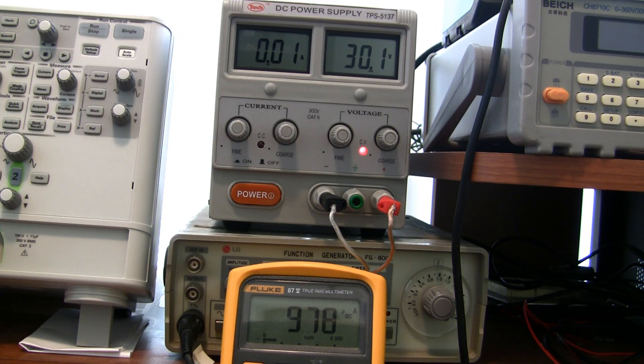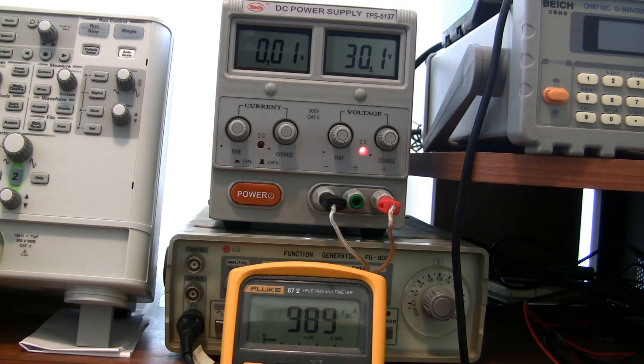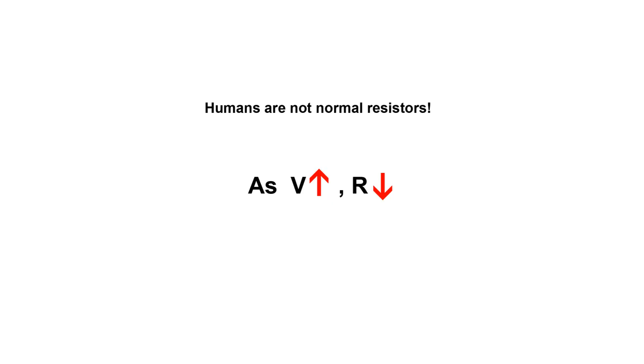From personal experience, I can tell you that 50 volts is where things start getting really painful. Remember what I said, as the voltage increases, the effective resistance of your body decreases, so the danger gets exponentially worse. And if your skin gets pierced by a sharp wire or a high voltage arc, the resistance of your body drops dramatically, so you don't even have to have hundreds of volts before things start getting dangerous.